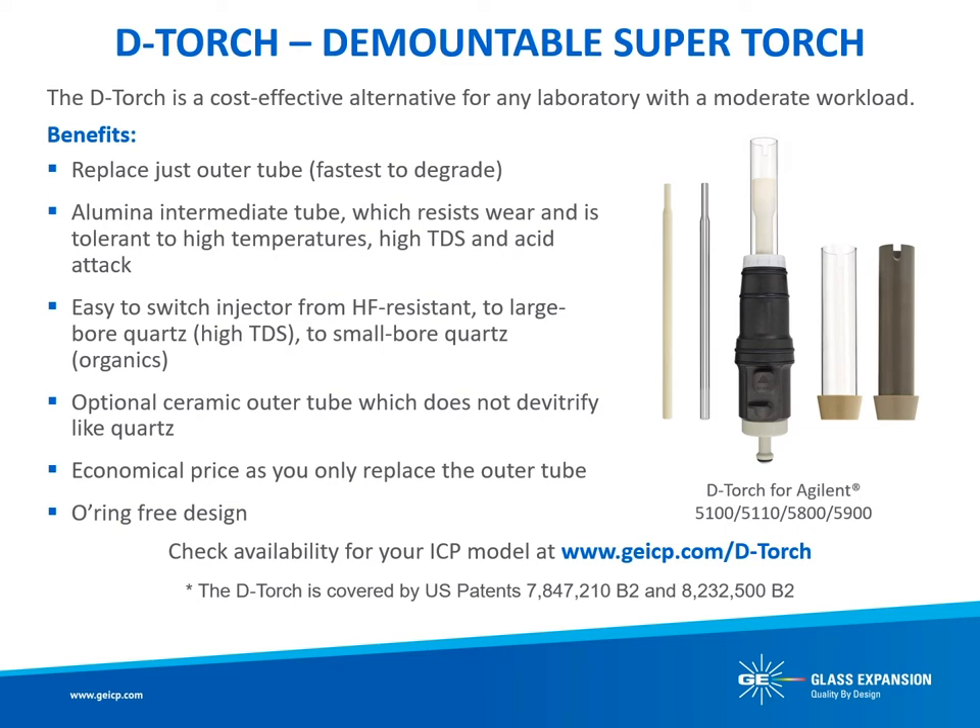Each D-Torch model is designed with a base that provides the same self-aligning, turnkey installation for ICP models such as the Agilent 5100, 5110, 5800, 5900, the Perkin Elmer Avio 200 and 500, the Thermo iCap and iCap Pro, and the Spectro Arcos and Spectro Blue. Compared to other demountable torches, the D-Torch also offers easier cleaning and maintenance with the ability to remove the injector and outer tube, and no O-rings to degrade or go brittle.